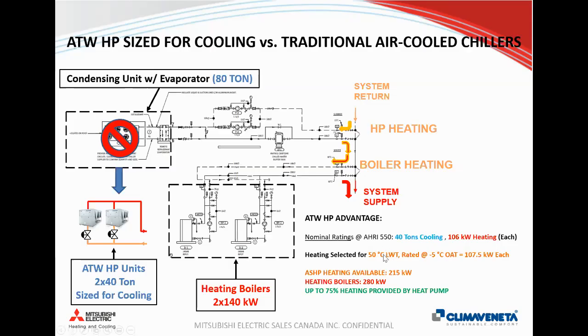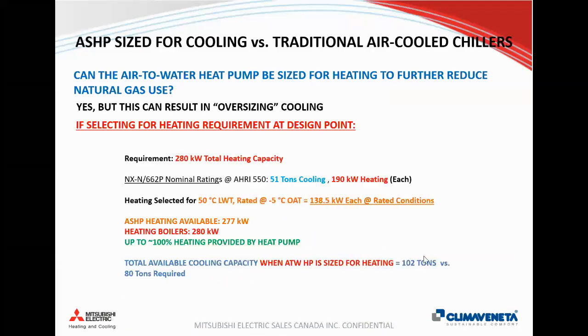So again, if you visualize the building load versus outside air temperature, the 280 kilowatts is really at your design temperature in Toronto of minus 23. Since we're looking at using the heat pump here only down to minus 5, chances are the heat load at minus 5 is below 75% of the peak heating capacity anyway. So it works well in the system to still offset heat. Basically from minus 5 to whatever temperature they're going to change it over afterwards, it's all savings, eliminating natural gas from the heat pump.